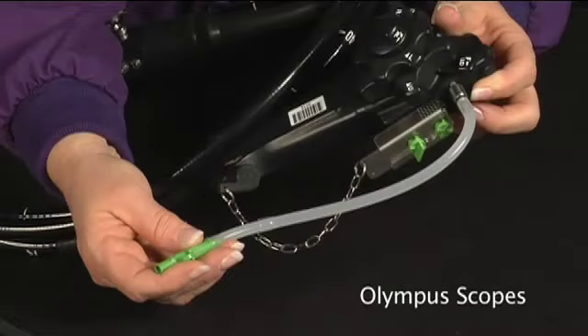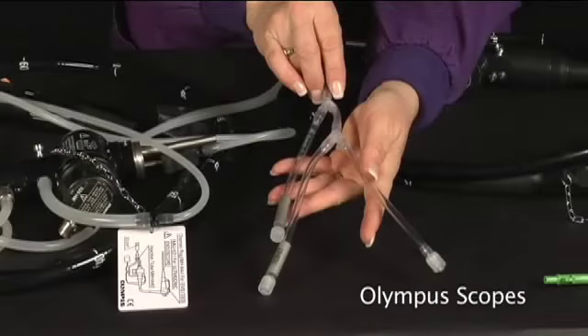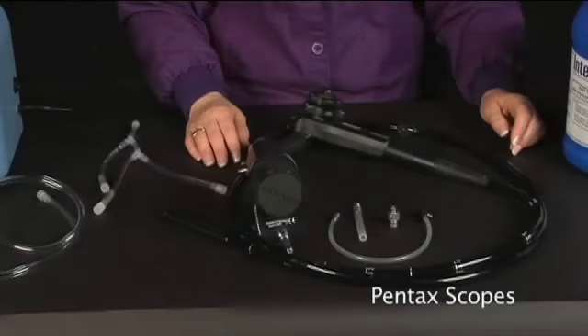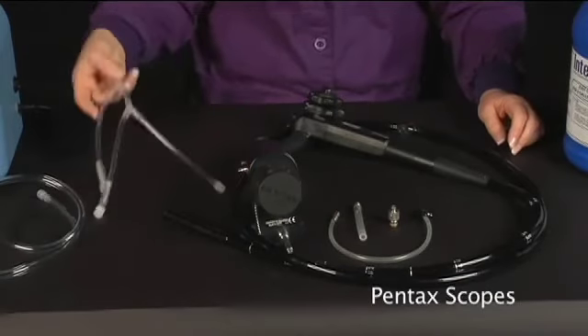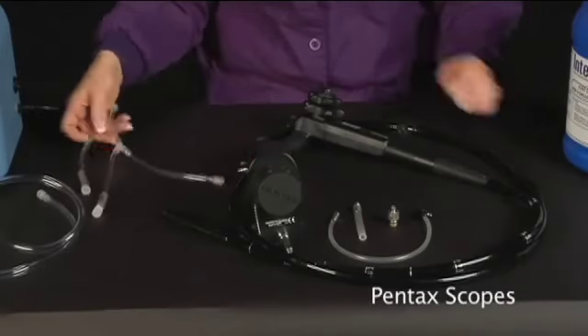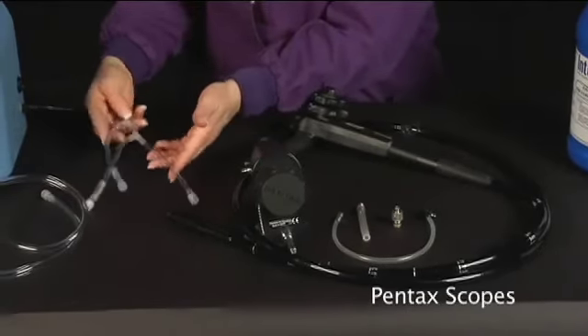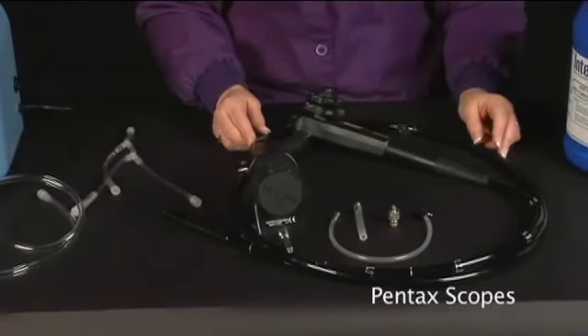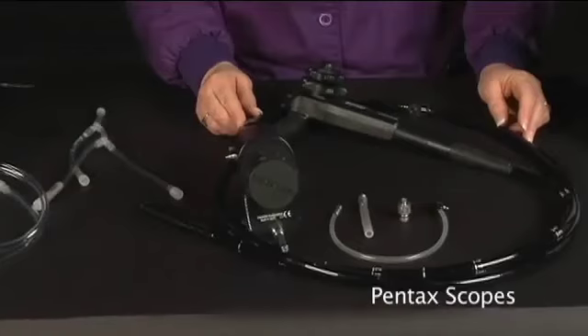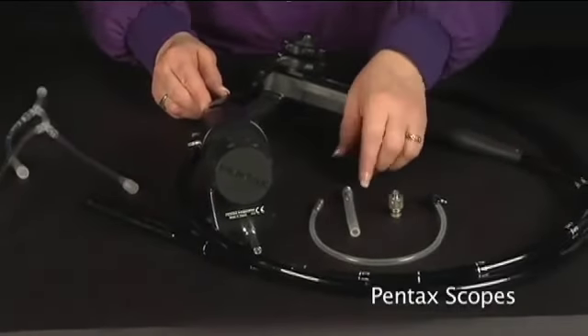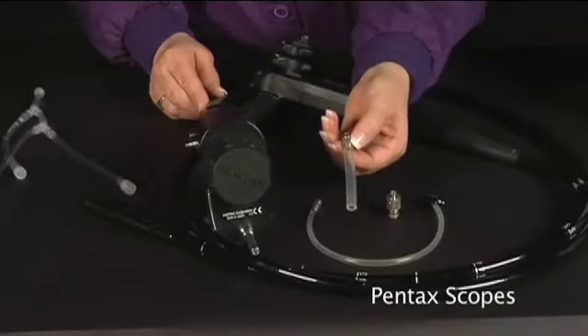The elevator wire channel of an Olympus duodenoscope does not require the use of the elevator wire channel hookup and can be flushed simultaneously with the other channels using the 3-way adapter attached to the Olympus channel irrigation tube and the elevator wire channel flushing tube. For Pentax endoscopes. To flush a Pentax gastroscope or colonoscope with a forward water jet, use the 3-way adapter and connect one end to the suction port. For Pentax 70 series scopes, the Pentax suction nipple adapter OE-C8 needs to be used on the suction channel. For Pentax 30 series scopes, the adapter connects right to the suction port.